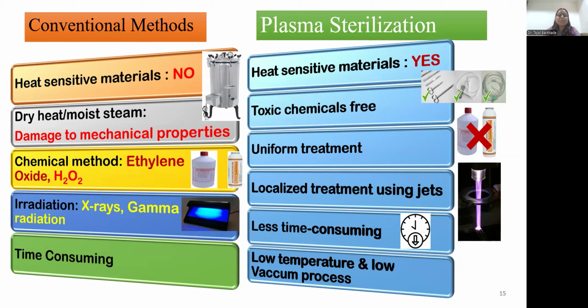That's why we can sterilize heat sensitive material in plasma sterilization, and it is also toxic chemical free. Again, we are not using any chemicals or toxic gas to form a plasma. So there is no question of residues of those chemicals, which can be harmful to the environment after the sterilization. And we can give uniform treatment to all surfaces and objects, which can be further used for surgical and medical treatment, and localized treatment using jets. If it is not a vacuum chamber plasma treatment, and you want localized treatment of any particular object, then we can use a plasma jet.